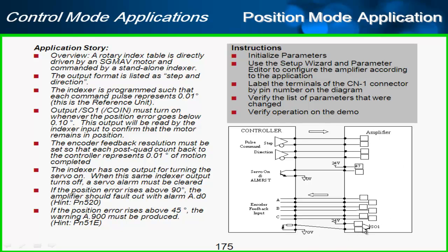We have the output SO1 connected here. We want that to turn on whenever the position error goes below 0.1 degrees. And we'll use that in the indexer controller to confirm that the motor is in position at the end of the move.